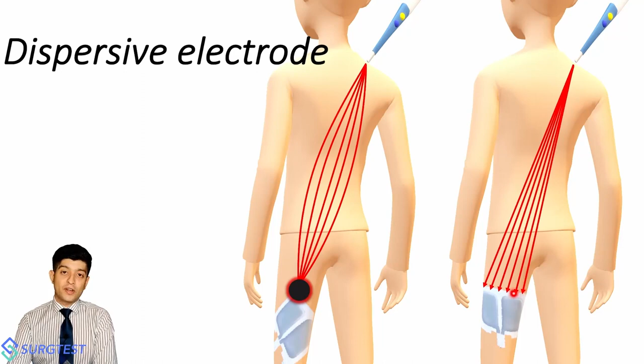The correct way of applying a dispersive electrode is with a long flat edge towards the area of interest which is being operated upon. So you get a good dispersion of the energy on this side, and you get low current density and lesser likelihood of any burns. Remember to always apply the dispersive electrodes over a well vascularized muscular area with a long edge towards the operative side.